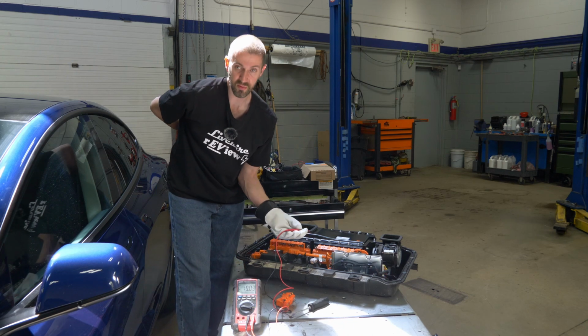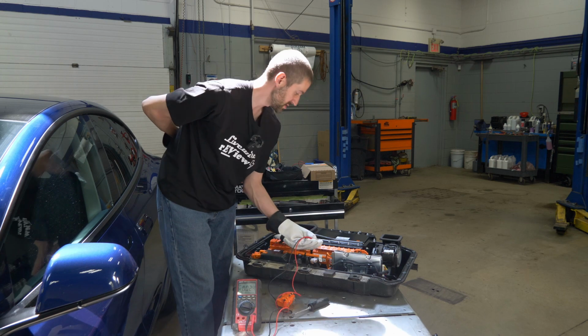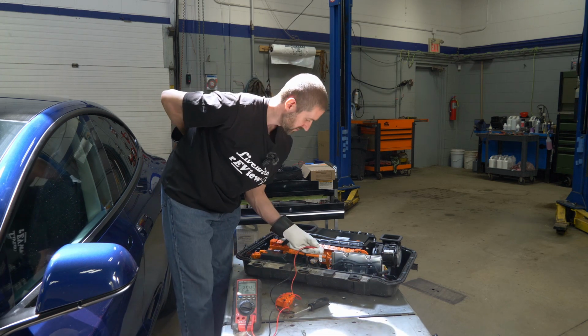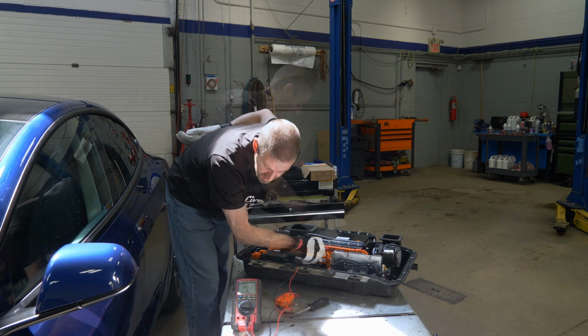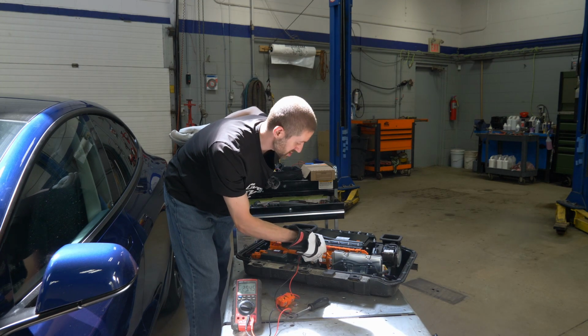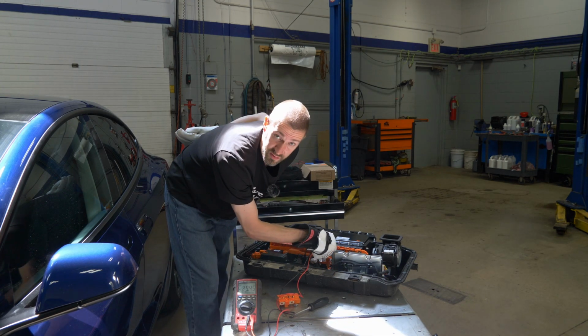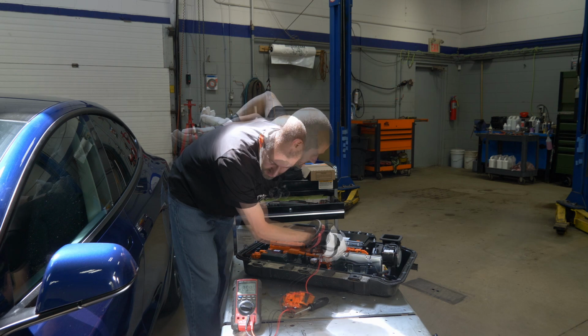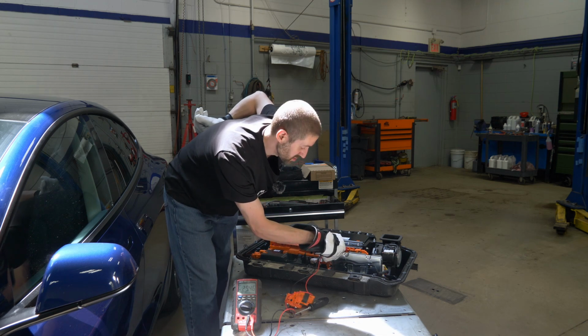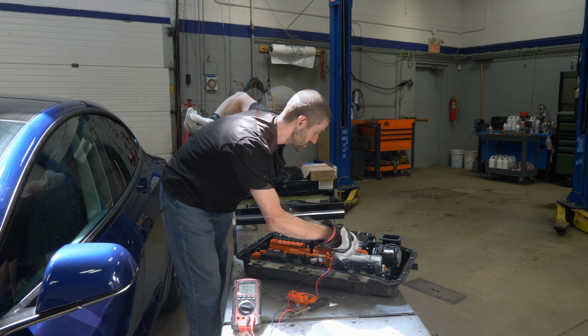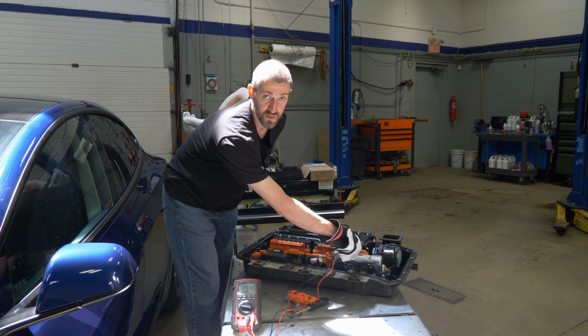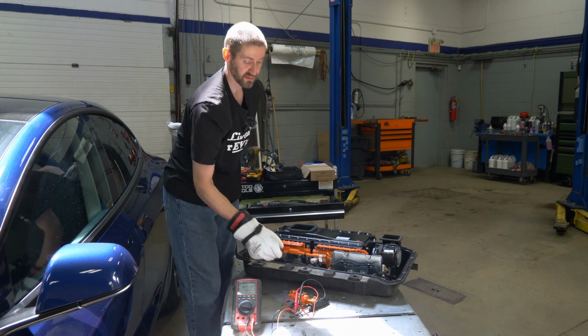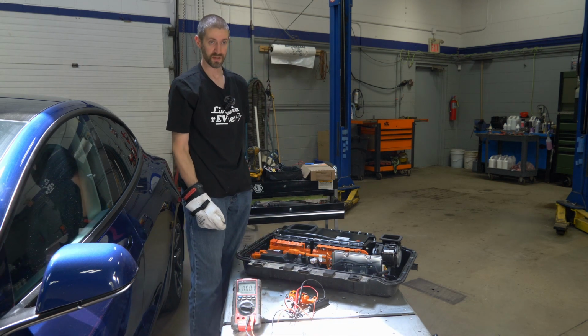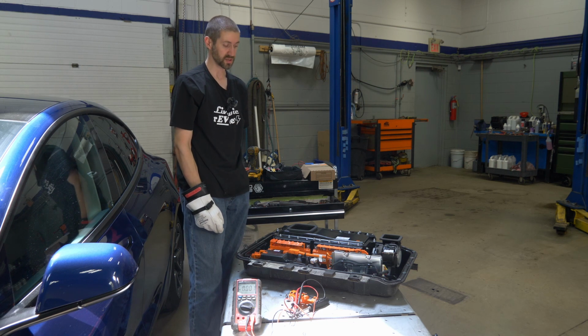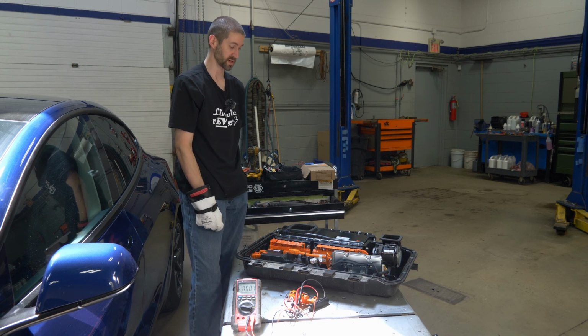29.4546. It's only off by 0.01 of a volt on that one. 29.45 volts, 29.45 volts on this section as well, 29.45 volts, 29.46 volts within 0.01 of a volt, 29.46 volts. So there are only three modules and they're off by 0.01 of a volt, which means that the battery management system is doing its job in this battery and everything is working.